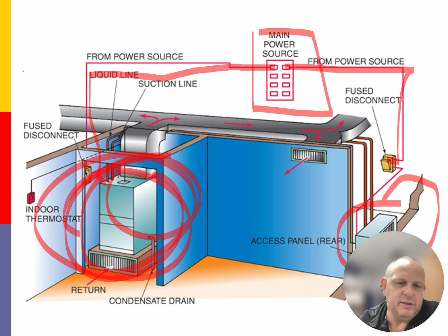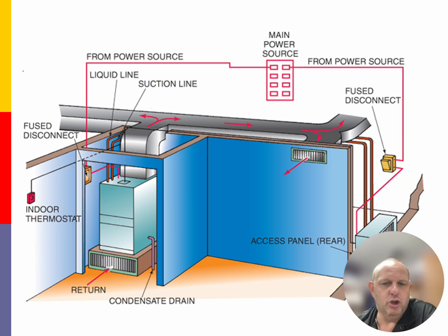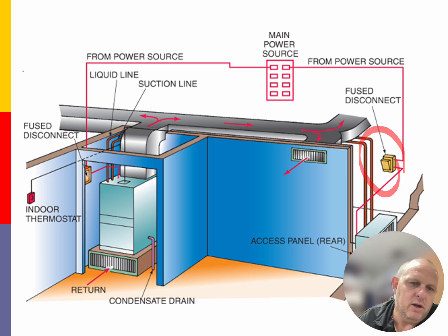So understand that along with running this, we'll size the breaker for the outdoor unit. We'll size the wire to handle the voltage and the amperage for that unit itself. We will install a disconnect for the high voltage to quickly shut off the power, both on the indoor unit and the outdoor unit. And then we'll hook up those wires to the appropriate locations within the indoor and outdoor unit, giving it its high voltage power.